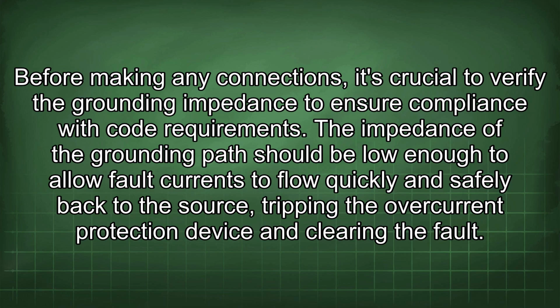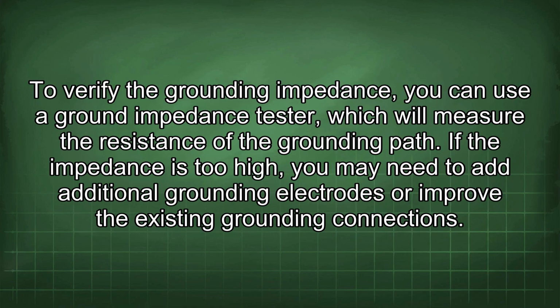The impedance of the grounding path should be low enough to allow fault currents to flow quickly and safely back to the source, tripping the overcurrent protection device and clearing the fault. To verify the grounding impedance, you can use a ground impedance tester, which will measure the resistance of the grounding path. If the impedance is too high, you may need to add additional grounding electrodes or improve the existing grounding connections.